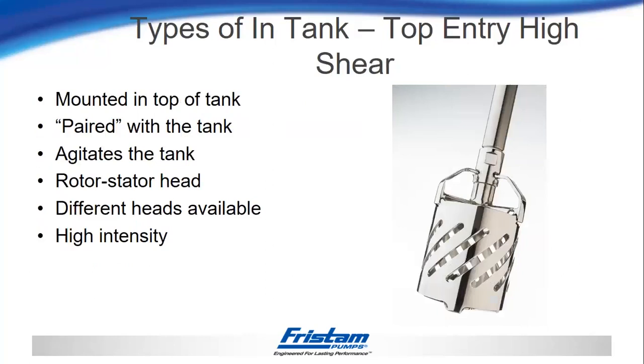The next type would be a top entry high shear mixer. Like the Lightnin mixer, this would be mounted to the top of the tank and paired with a particular tank design. In this case, we have a rotor stator head design — there's a rotor spinning inside a cage and pushing the product through the slots. Different heads are available with different slot sizes or rotor configurations, depending on whether you're dispersing solids or trying to create an emulsion. This would be more of a high intensity mixer with higher shear rates.